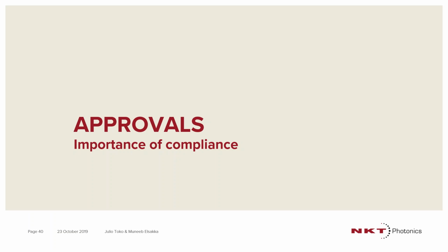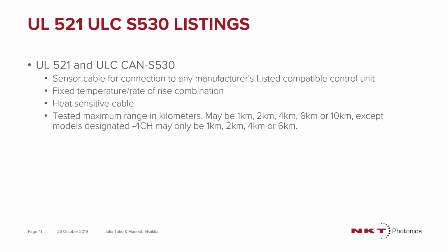Thank you, Julio. Now we'll be looking at some approvals and the importance of compliance and approvals in fiber optic linear heat detection. You have your UL approval body, so UL, more specifically UL 521 and ULC S530, which is the ULC equivalent. This is the standard for heat detectors for fire protective systems. It's definitely important for fiber optic linear heat detection systems to have UL approvals as well as other third-party approvals, testing for fixed temperature, rate of rise, and heat-sensitive cable. And you definitely have to have the cable listed with the controller.